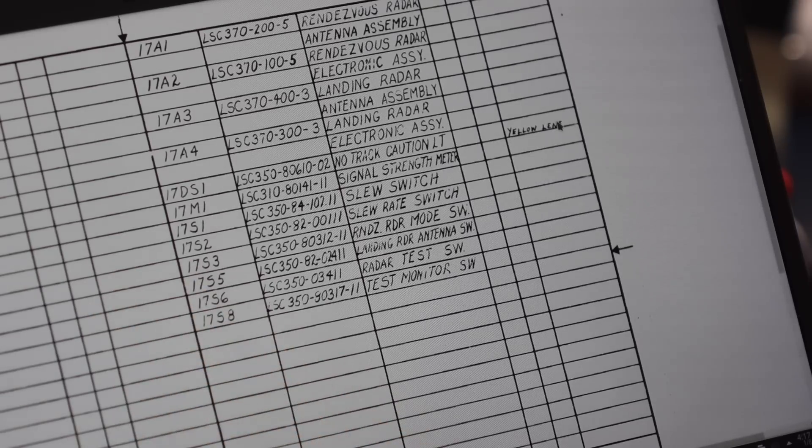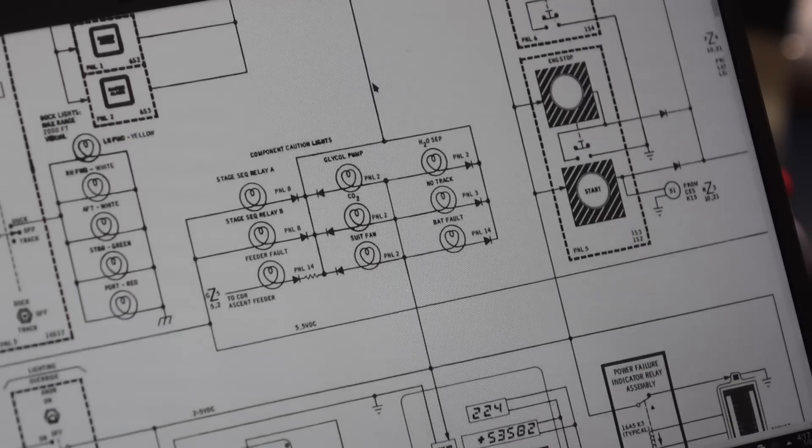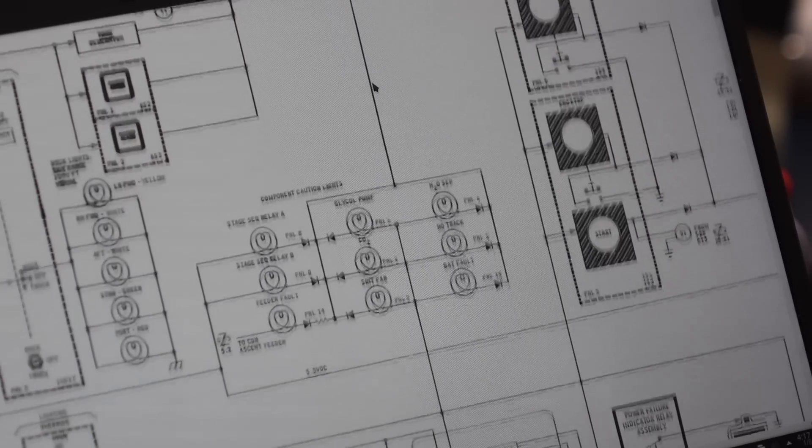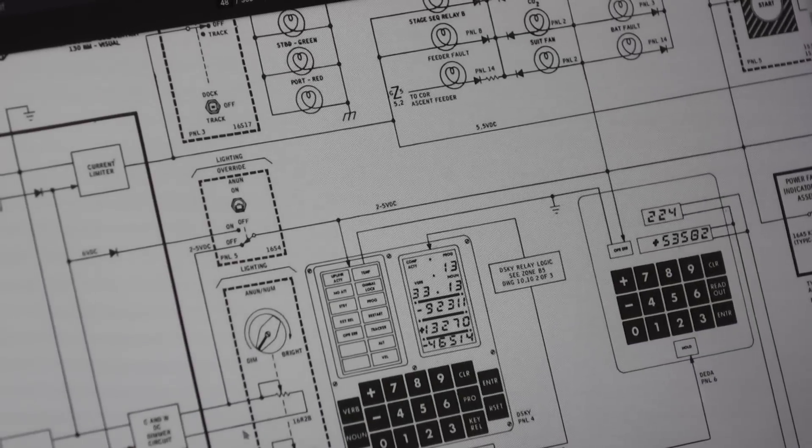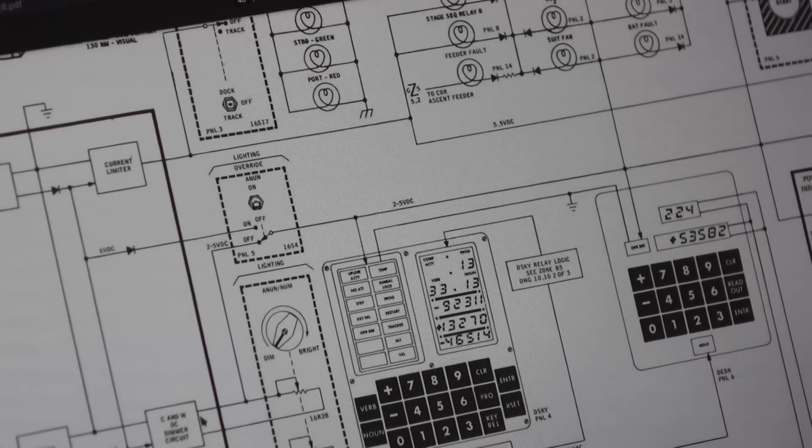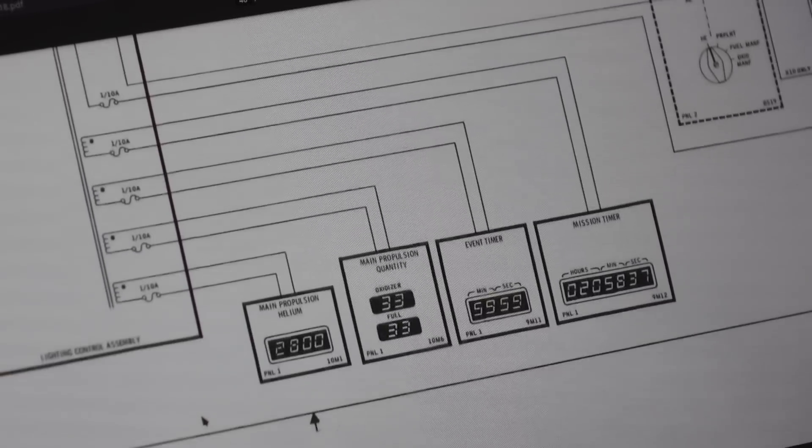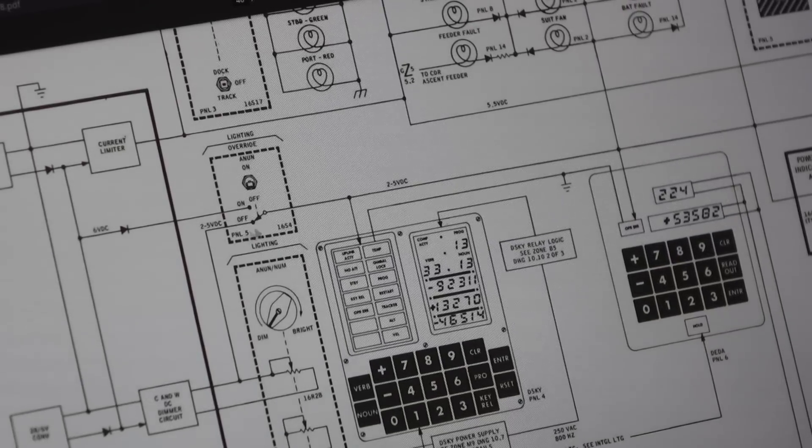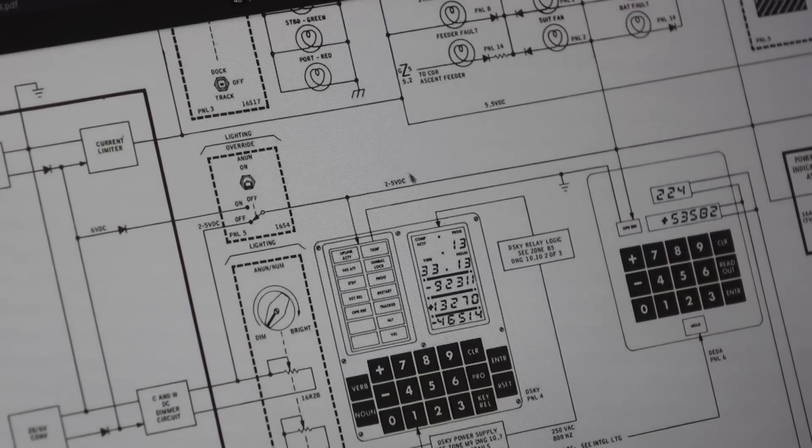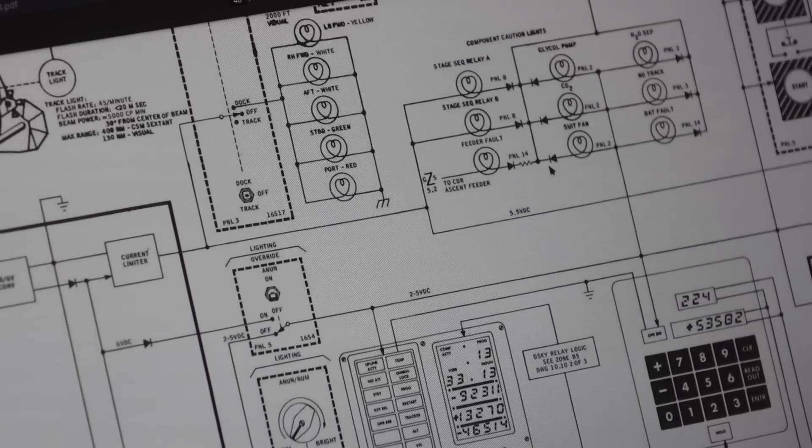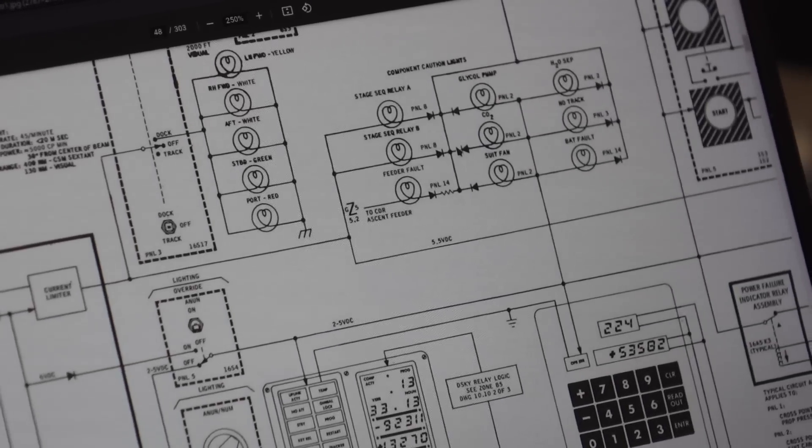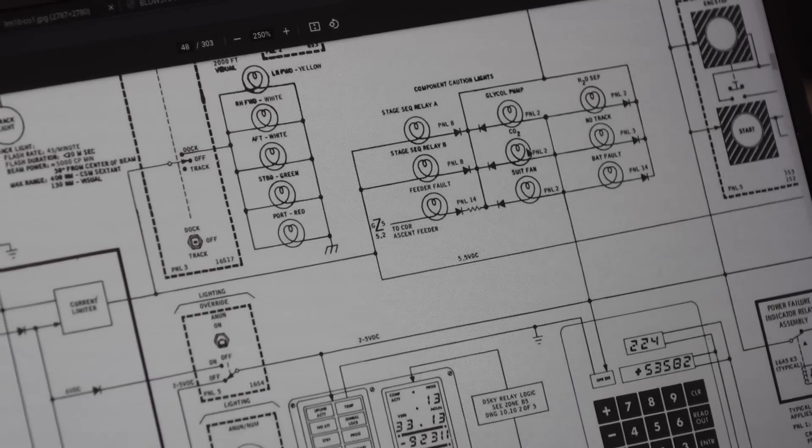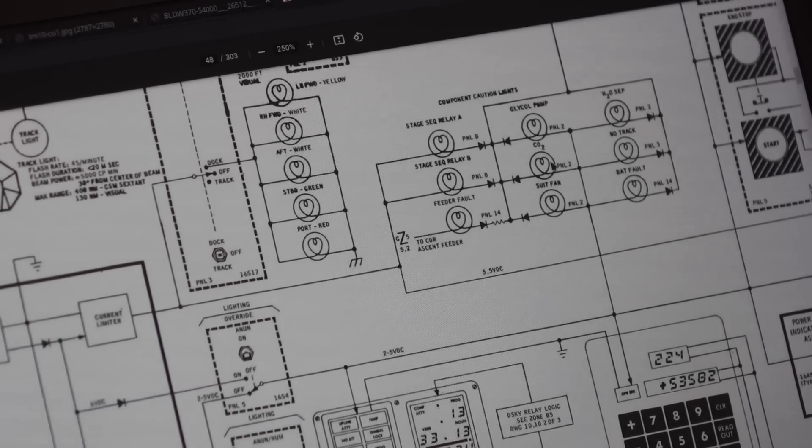They came in red too, I think. This is sort of systems level how they're wired up. There's a caution warning DC dimmer circuit in the lighting control assembly that dims from 2 to 5 volts. So these lights have 5 volts on their power pin always.